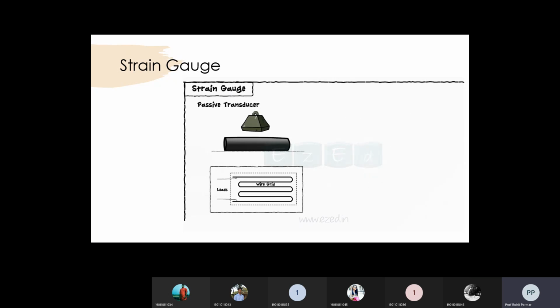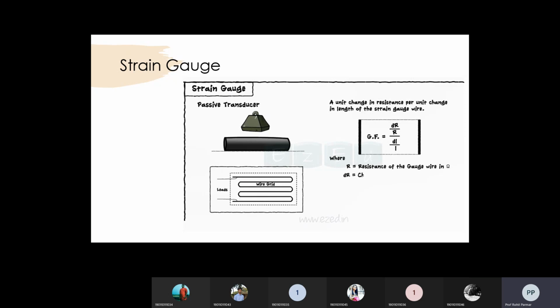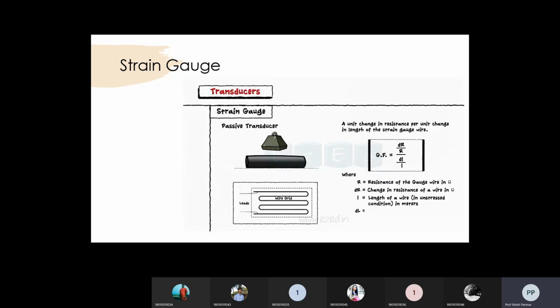The characteristics of the strain gauge are measured in terms of a gauge factor, which is defined as a unit change in resistance per unit change in length of the strain gauge wire. It is given by a formula GF equals dR upon R upon dL upon L, where R equals resistance of the gauge wire in ohms, dR equals change in resistance of a wire in ohms, L equals length of a wire in unstressed condition in meters, dL equals change in length of a wire in stressed condition in meters.